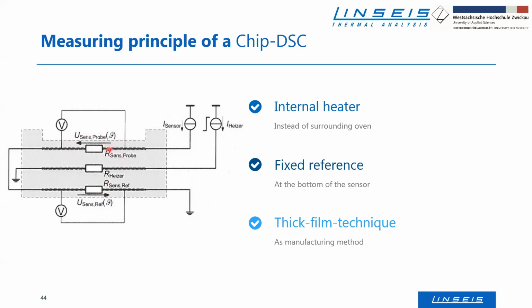And if anything is happening inside your sample, if you have an exothermic reaction, then it's getting hotter on that side, and a heat flux from the sample to the reference side is bringing that delta T between the reference and the sample again to zero.